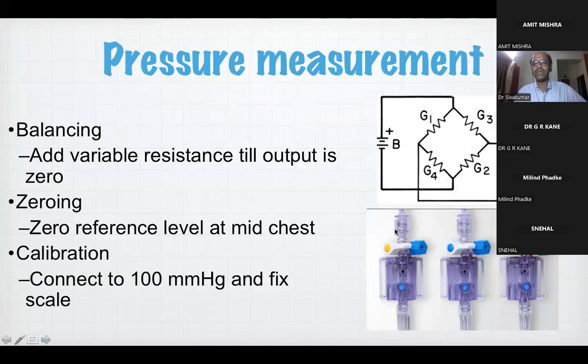Now, this particular transducer that you see, you all will be very, very familiar. If you look at these transducers, basically a long catheter through a connecting tubule of 100 centimeter will be connected into these points, and you will be seeing these small micro transducers in your cath lab. What you see here is a black color dot. So that is actually the membrane of the transducer. So whenever the blood column moves, the fluid transmits that pressure and it starts moving this diaphragm. And when this diaphragm moves, imagine that here is the diaphragm. The diaphragm will go down and up.